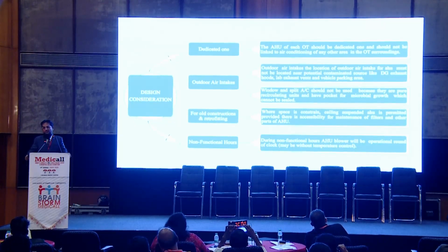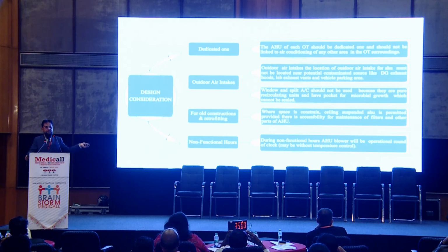These are the things given in the NABH guideline. From the design point of view, they mentioned that the AHU of each OT should be a dedicated one. It should not be combined with the adjacent area. That is more important, because infection from other rooms may come to your OT. Then they said the outdoor unit should be kept in a place away from the DG exhaust or the parking area where dust is generated. Because of that, your outdoor unit may get choked, the condensing coil may get choked very fast, and cooling may get hampered.